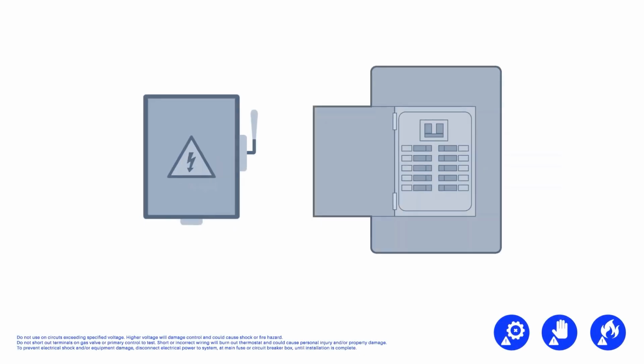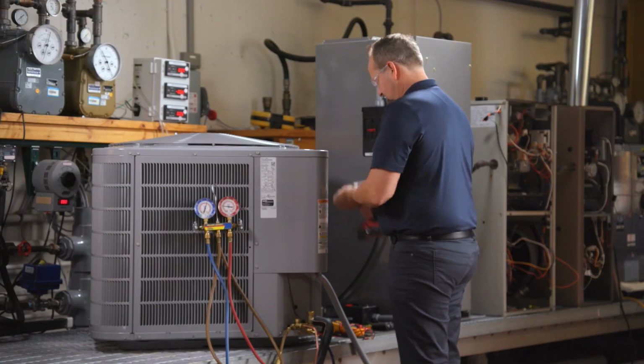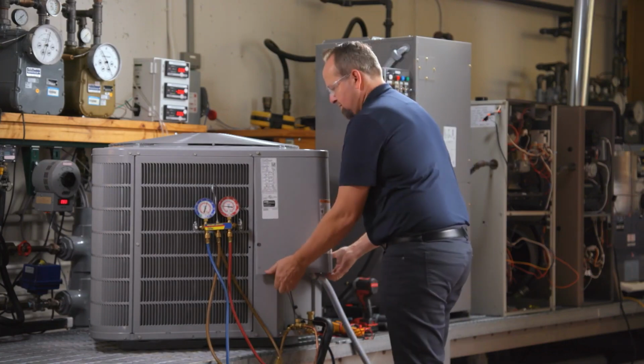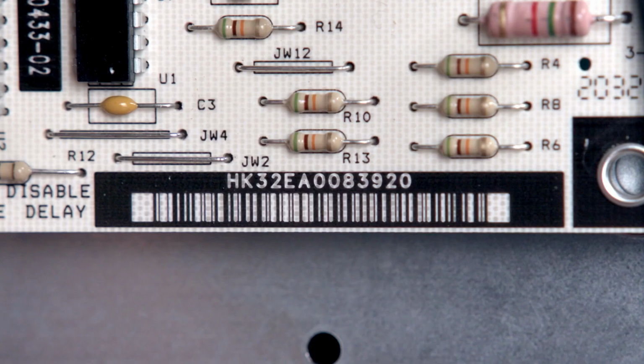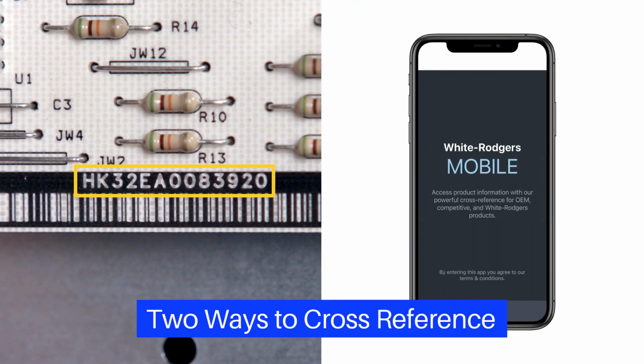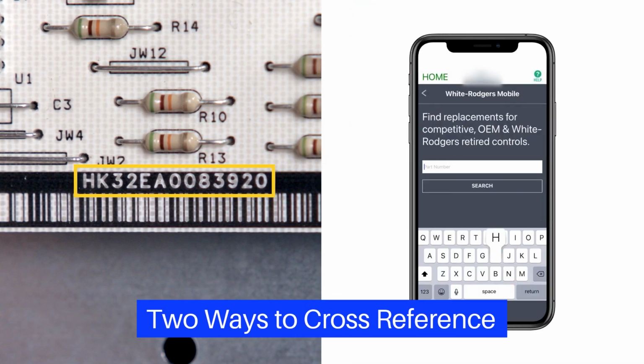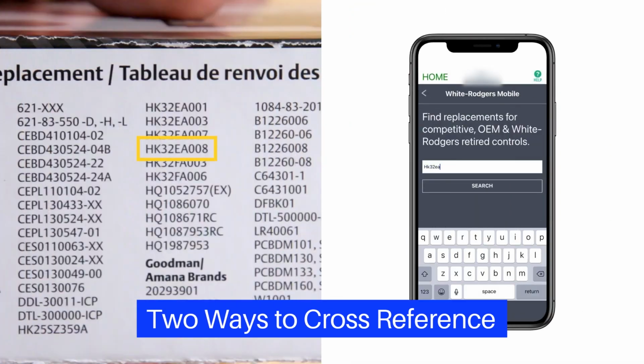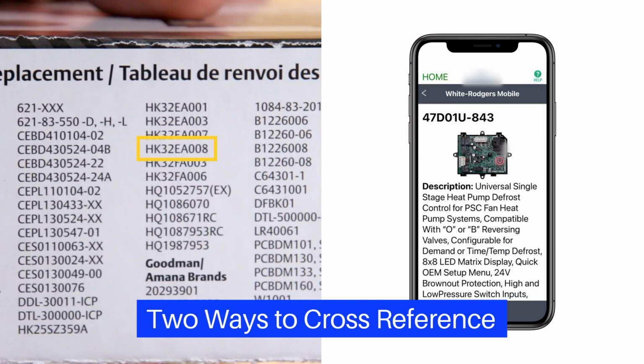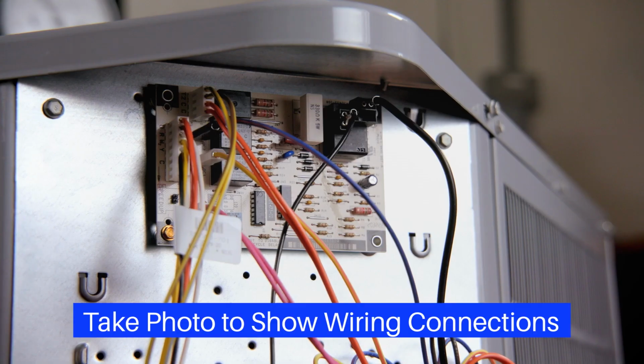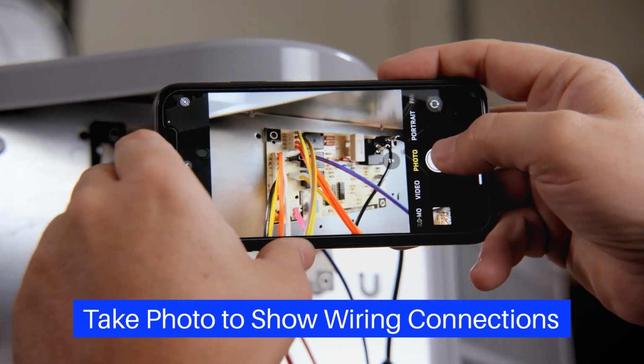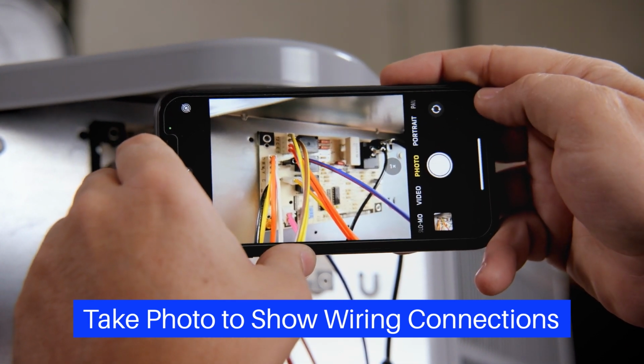First, ensure the power is disconnected from the heat pump condenser and the air handler prior to servicing the unit. Remove the unit service panel and open the unit for internal access. Check the part number on the existing control and verify it can be replaced with the 47D01U843 using the cross-reference on the side of the box or the White-Rodgers mobile app. Take a picture of the existing control for reference before disconnecting wires.